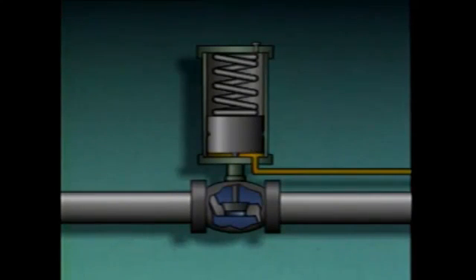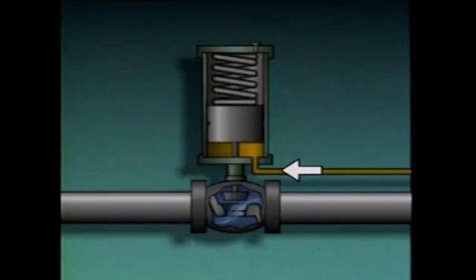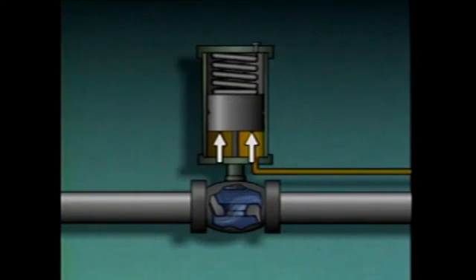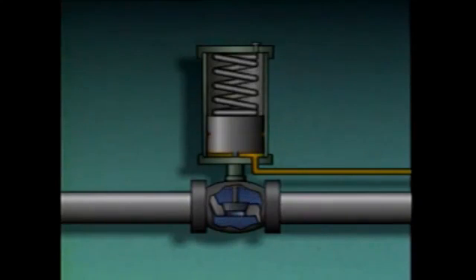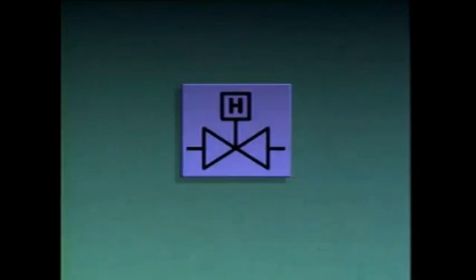The piston can be positioned anywhere in the cylinder by controlling the amount of fluid entering or bled from the cylinder. This actuator is considered single-acting because fluid enters through only one port and acts on only one side of the piston. It is also described as spring-return because a spring forces the piston down to close the valve. If hydraulic fluid pressure is lost, the spring will cause the valve to fail closed. On a piping system diagram, a single-acting hydraulic actuator may be represented by a specific symbol.